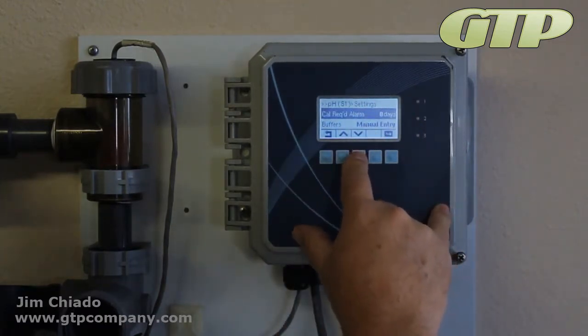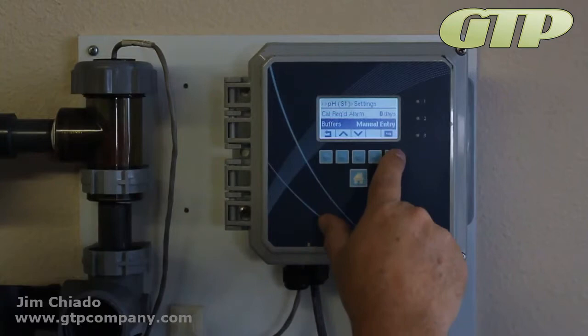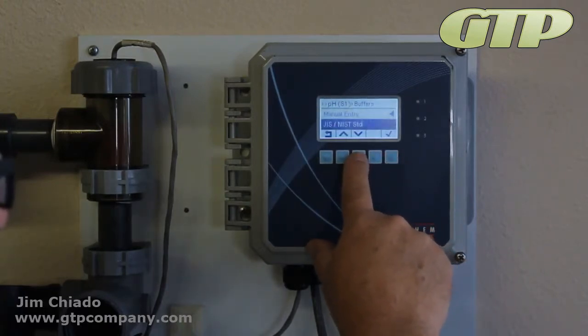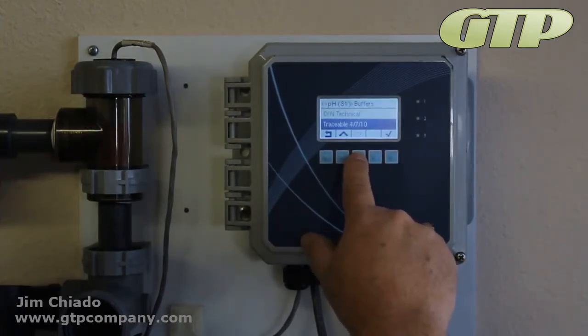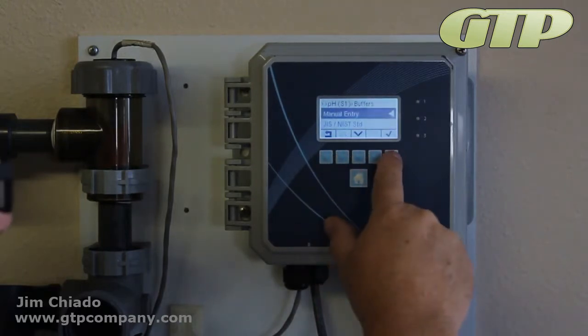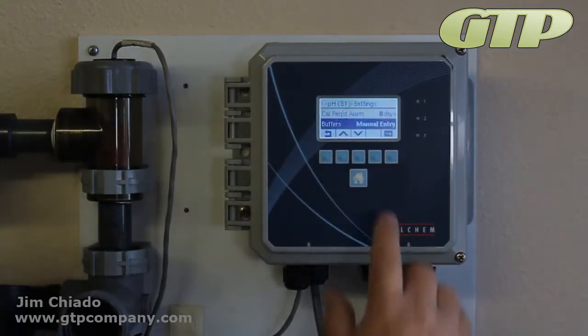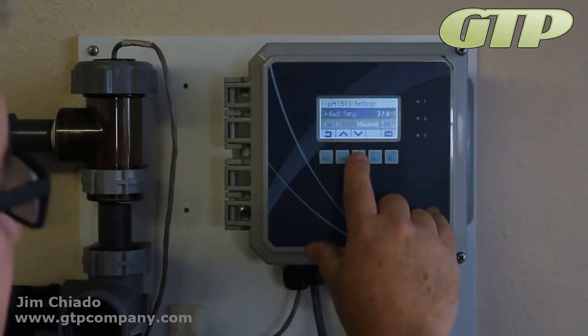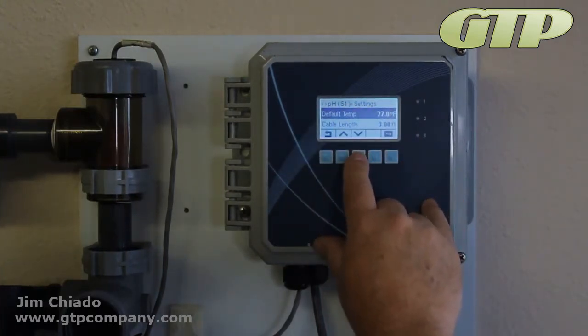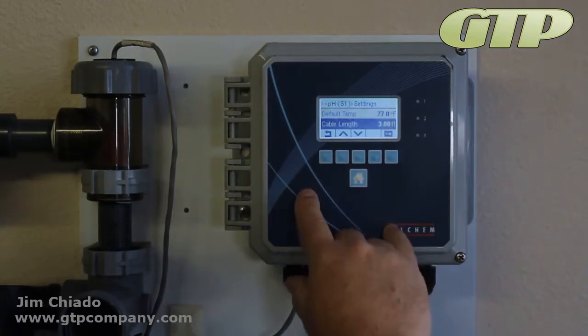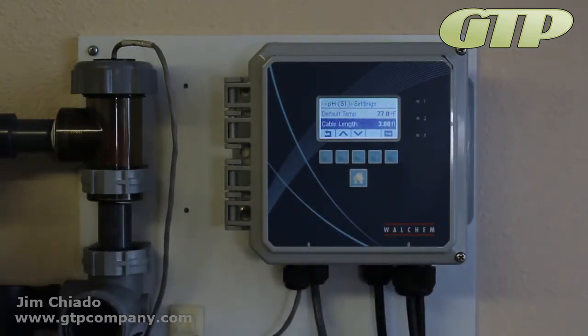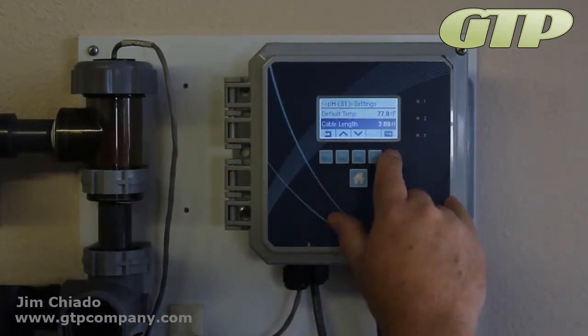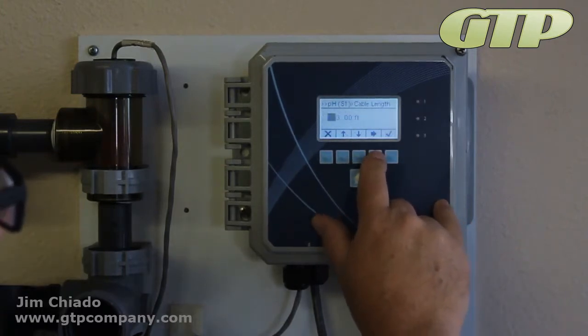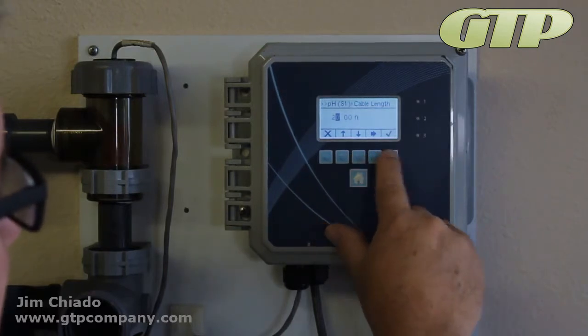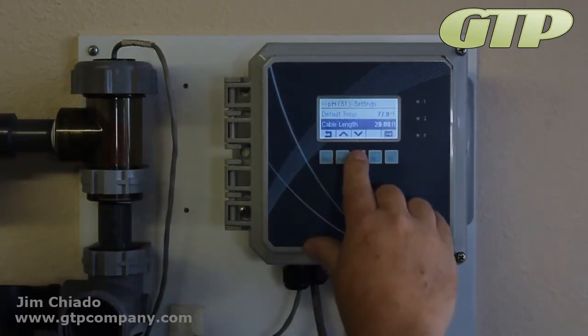Cal required, it'll remind you. Buffers, you can manually enter the buffers, or you could have it use NIST standards, traceables, you could do all those things. I leave it on manual just because we don't really do those things, but your customer may need them. Default temperature, 77 degrees or room temperature. Cable length, this here is a 20-foot cable. Normally you'd have a 3, but we're going to change it just so we have a little bit more clarity when we do our calibrations, which is going to be in the next one.